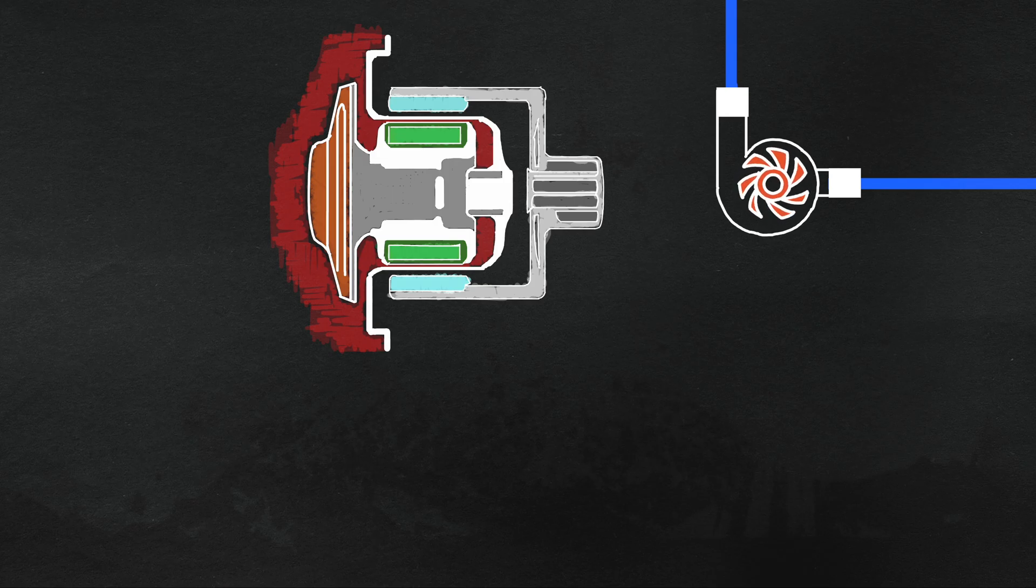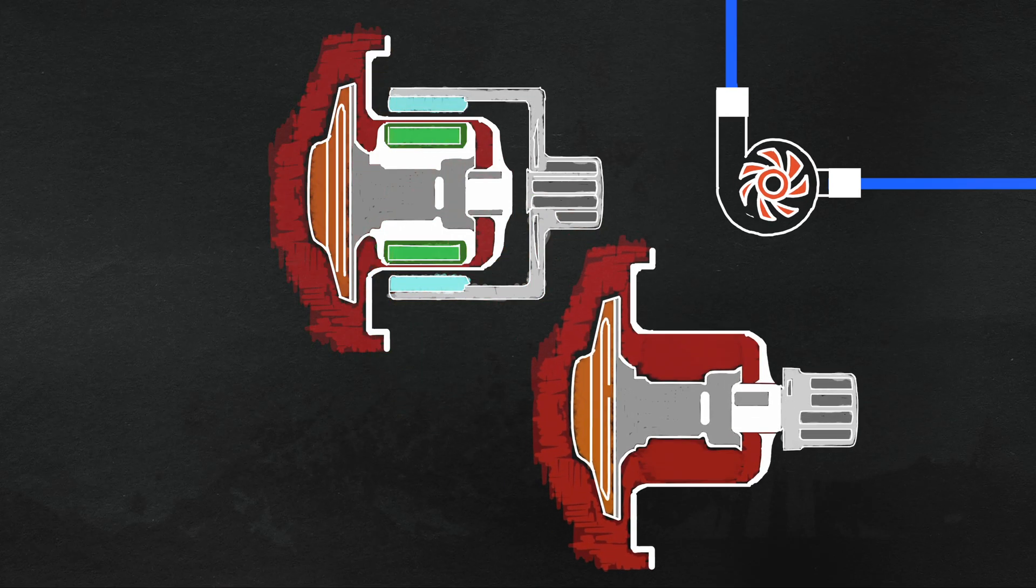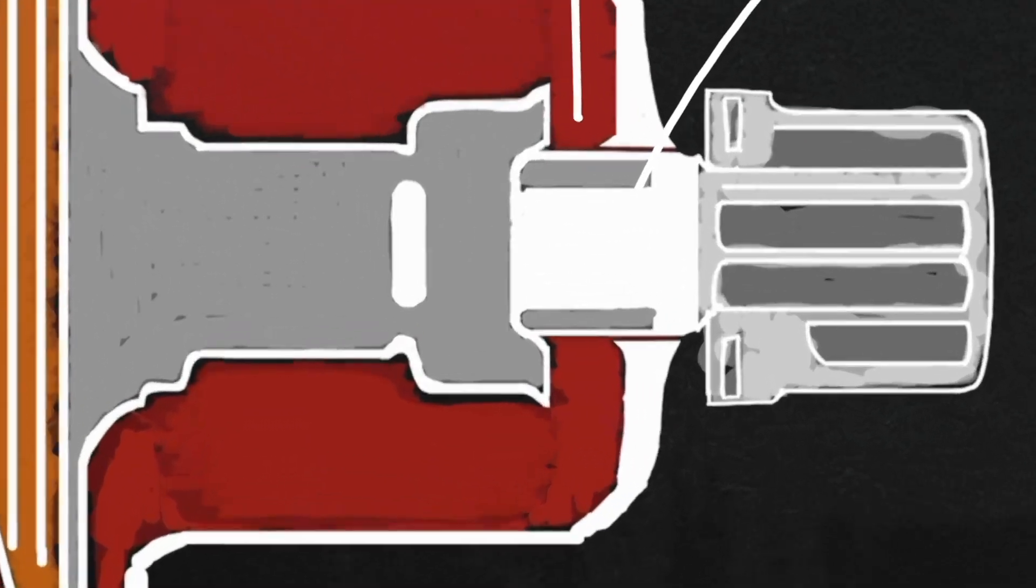Another innovation usually seen in these pumps is the magnetic coupling for non-contact transfer of torque, which will keep the blood sealed and less prone to blood leaks around the shaft.